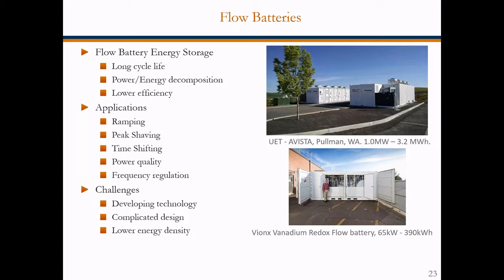So when you talk about recycling a flow battery after you're done with the project or the stacks go bad, you could take the electrolyte, sell it back to the battery manufacturer, and utilize it in another system. The business model of flow batteries is moving toward just renting the electrolyte, where the owner of the battery system pays a monthly fee or whatever is negotiated, and at the end of the project, the battery vendor takes the electrolyte back and moves it on to the next project.